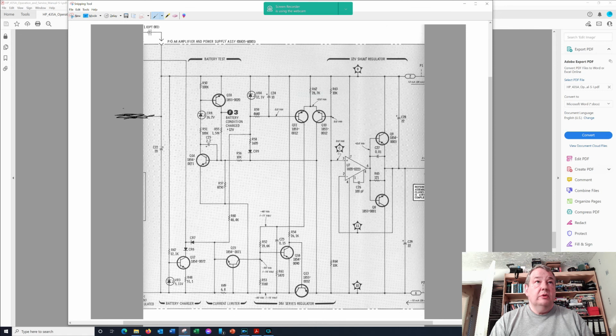So just here we've got the plus in, and down here we've got the minus in from the bridge rectifier, and we've got a bit of a battery switch circuit up at the top here. Okay, now mine has not got a battery in it, just to be clear on that point. Okay, and our symptom is that the voltage is going to about 22 between test point 9 and test point 10. Okay, and it should be 24.